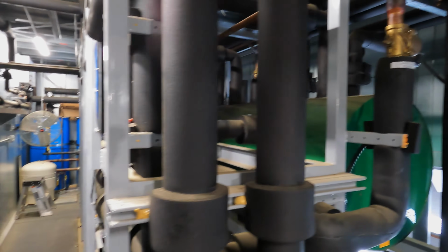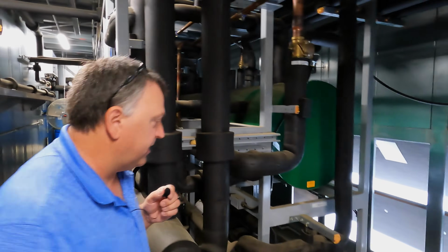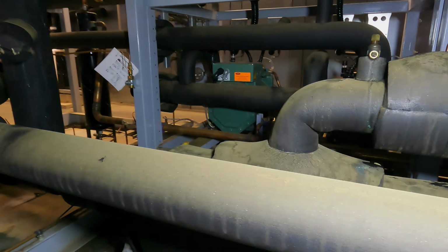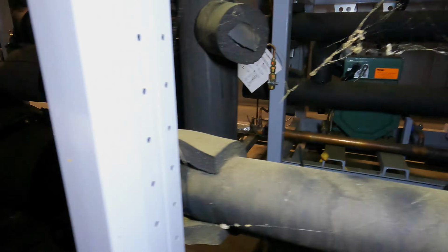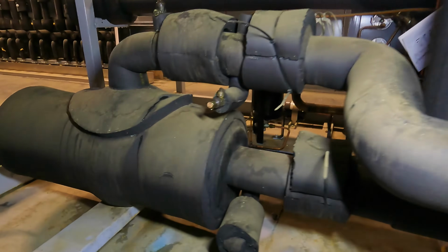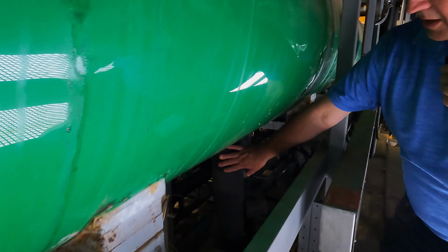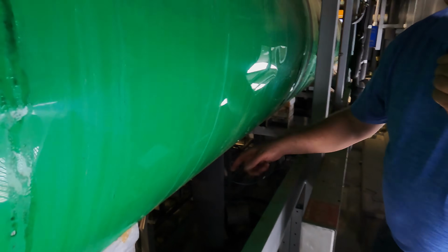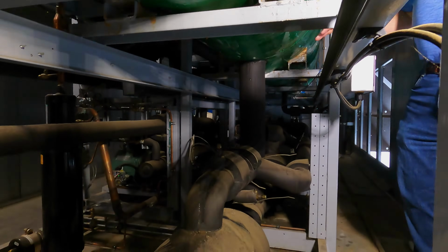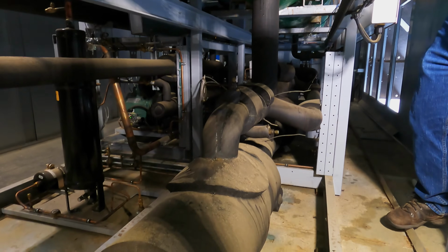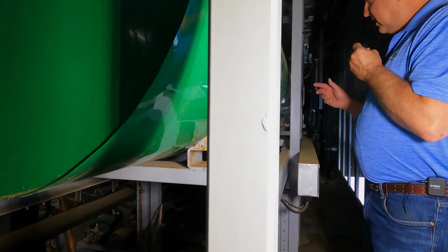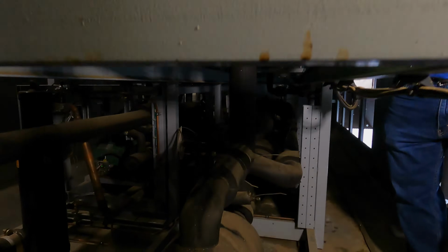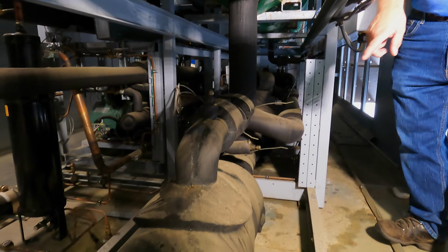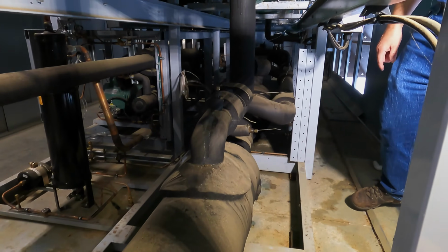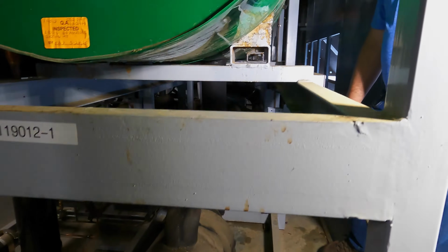Once it's a liquid, we have pumps. Come over here, I'll show you. We have 2 pumps. They do not run at the same time, only one at a time. And it's taking liquid CO2 from the bottom of the vessel to one of our pumps. It's very critical that at least one of them is running. As you can see, we have it insulated because it would sweat like hell. By the way, these are not cheap pumps. They run a good $10,000.